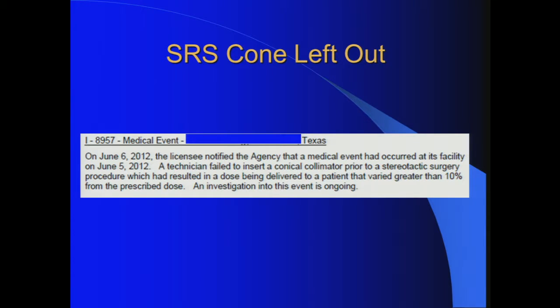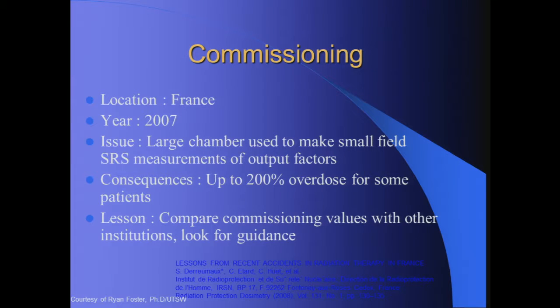Another situation: the cone, you have the insert, and then the cone goes inside that, was left out. A technician failed to insert a conical collimator prior to stereotactic radiosurgery, which resulted in a dose delivered to a patient that varied greater than 10% - a lot more than 10%, and that was actually their cutoff criteria.